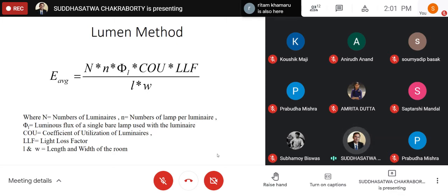50, 60. They need more lights. And lastly, the condition is that the speed and accuracy of the job is required very high. So that's how the 300, 500, and 750. Because the general thumb rule says that if you are not able to define under which class you are falling, it is preferred that you go for the middle value, the 500 one.